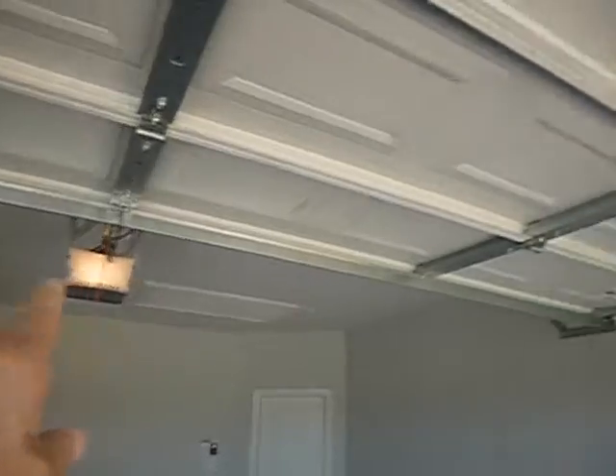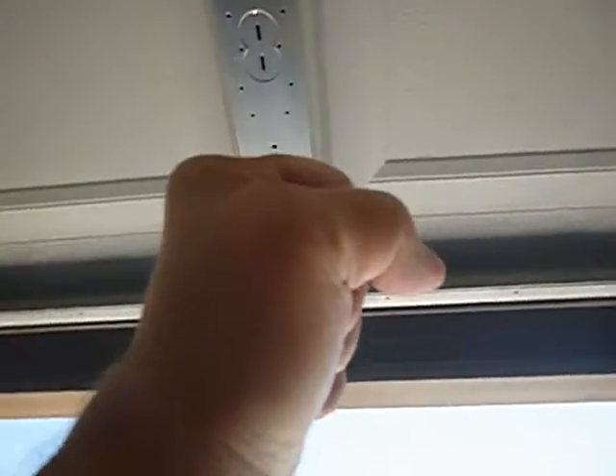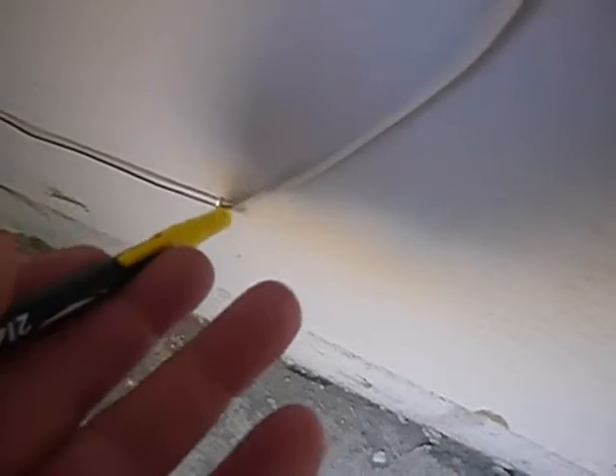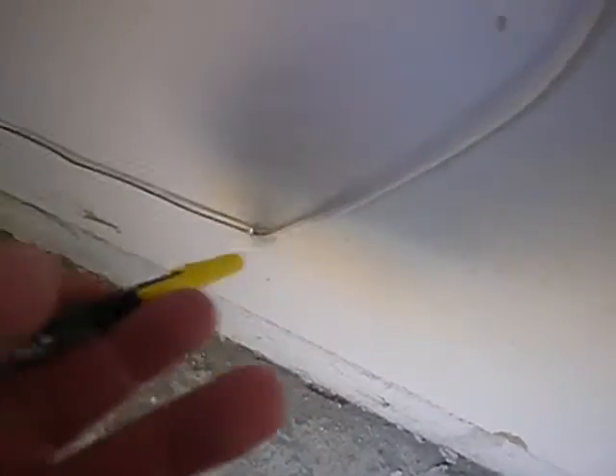In line with the motor, there should be an opener handle, so that when you go into manual mode, you can pull it up with a handle. We don't have one. The optic sensors are low enough, but these control wires, those staples are not insulated. The metal edges of the staples can eat the insulation, chew it, and cause damage. They should be insulated staples for that.